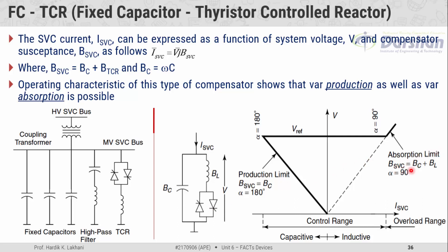When alpha equals 180 degrees, the antiparallel connected thyristor pair is considered as an open circuit element, so there is no current flow through the inductive branch. The SVC current only flows through the capacitive branch, and the net susceptance offered by the SVC equals B_C. Since all capacitive branches are directly connected without any control, maximum reactive power is produced into the system, and the limit corresponding to alpha equal to 180 degrees is known as the production limit.